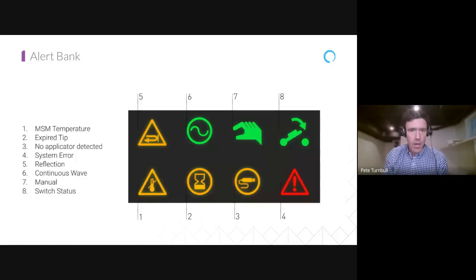Okay. Then we talk about the alert bank. Don't need to worry about this or any of these because you're going to be using the handpiece. So that's all irrelevant. That's your reflection error, which we've talked about. The temperature is not something you're going to have to worry about. This is an expired tip alert. So if you put on a tip that's previously been used, it's again to reduce cross-contamination. If you put it on and it's been previously used, it'll tell you that it's expired and it's no good.